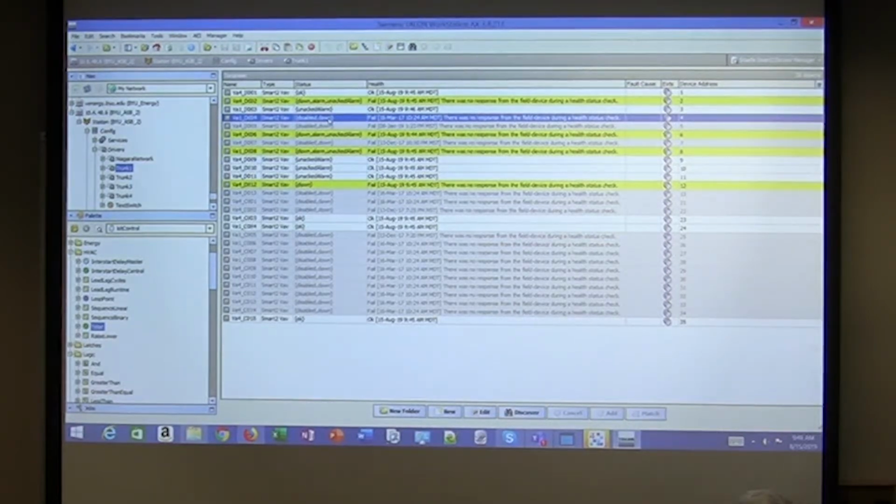And he responded back, nope, I'm a DDC card. And so it'll mark it orange. Or if it gets garbled information back, he didn't understand it, he'll mark it orange. When he marks it orange, he doesn't ask it for anything again, because he says, I've got the wrong controller or it didn't respond right. I don't know what I should do. So you usually have to right-click ping the orange ones to get it to re-query and then come back.